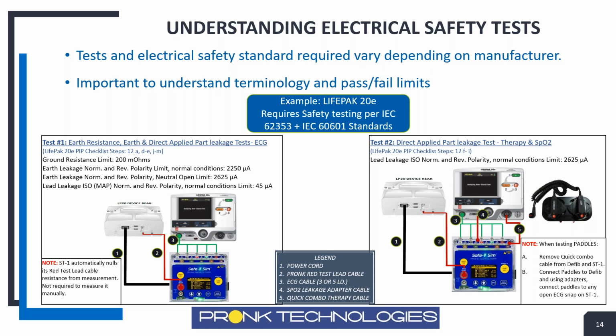Why? Because it has a different limit. You can see here for the lead leakage test for the ECG only, the maximum lead leakage limit is 45 microamps, which is pretty low, which is what you want. But if you're testing the therapy cable and the SpO2 cable, you're allowed up to 2,625 microamps. That's considered a pass. So it's higher than what you would normally think, but it's perfectly acceptable on this device. So this is yet another test unique to this one particular brand.